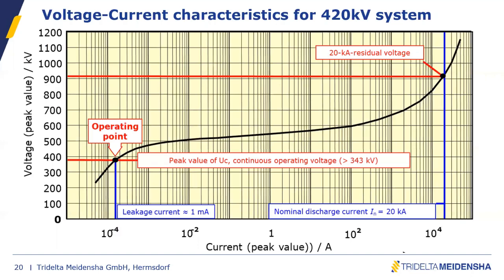And before giving you an example of bad configuration, to make sure the example is clear, I want to show you this curve. I'm sure that most of you are familiar with this voltage-current characteristic. On the x-axis you have the current through the surge arrester, and on the y-axis you have the voltage peak value across the surge arrester. So it's important to define two areas in this diagram. The first area at the bottom left should be called the operating area. And the area here on the top right should be called, I don't know, the protective area, because most of the time, the surge arrester, the point is in this area, right?